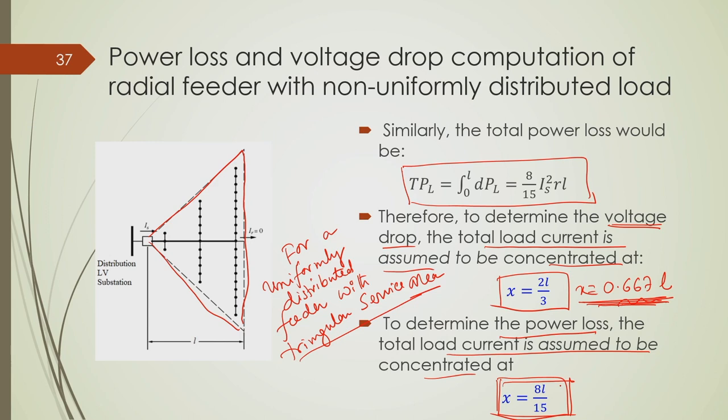In this particular lecture, I focused on the analytical approach to find out expressions for two important limiting factors — power loss and voltage drop — for two typical cases: a feeder with a rectangular service area and uniformly distributed load, and a feeder with a triangular service area and uniformly distributed load. We can understand how these voltage drop and power loss expressions differ from a typical lumped load concentrated at one point of the feeder. Thank you.